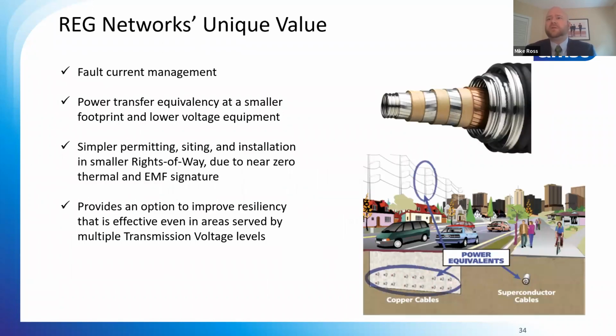As some of the other speakers have talked about the advantages of superconductor technologies, the key advantages for reliability and resiliency applications are the fault current limiting characteristics of the cables that the previous presentation discussed in detail. So that fault current limiting capability isn't just built into standalone fault current limiters, like Professor Noe was discussing, but it's also built into our cables, and that characteristic is really critical for some of the applications.